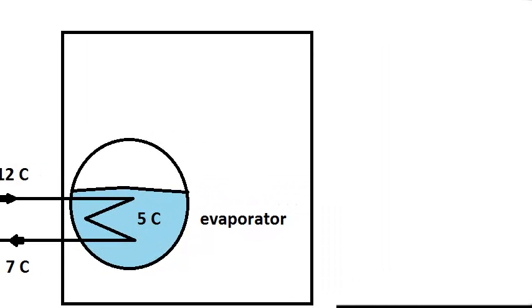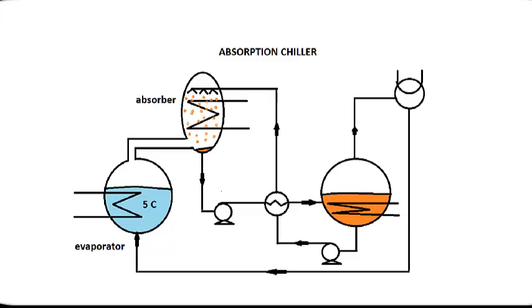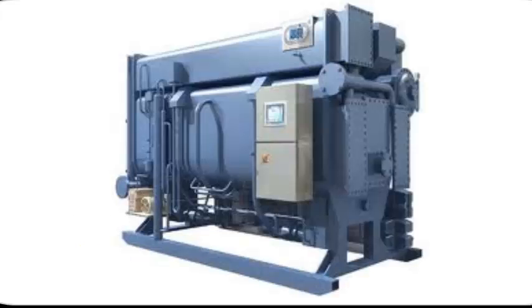This evaporator is part of an absorption chiller, which uses water as the refrigerant and an aqueous solution of lithium bromide as the absorbent fluid. There is no air or any other non-condensable gas anywhere in the chiller. It was evacuated and sealed with its charge of water and brine on the day of its manufacture. The only gas in any of the vessels is water vapor.